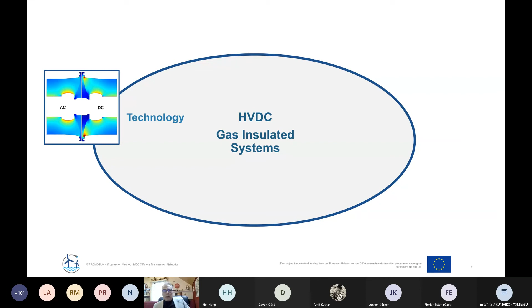But going more into the details for HVDC gas-insulated systems, looking at all the problems or issues we have to cover, the first thing is, of course, the technology. That is what you see here on the left. The field distribution in an HVDC system is completely different compared to an AC system. Here the resistivity of the different materials is of higher importance. Therefore, we have an influence of temperature and also of the electrical field itself on the field distribution inside the system.